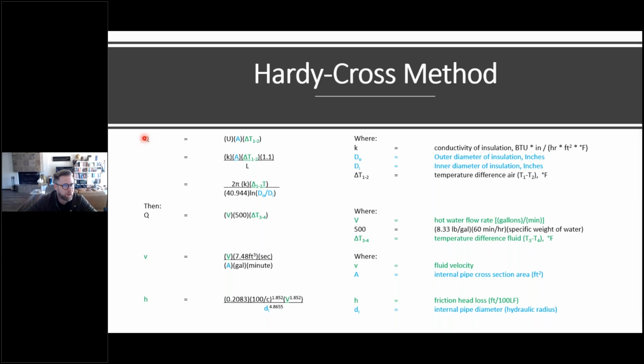So the first one is our conductivity equation, right? Q equals, when we simplify it out, 2 pi times K times the delta T of 1 to 2, divided by 40.944, and that logarithmic root of the outer diameter and the inner diameter of the insulation walls. Then we also have our heat transfer rate for our fluid flow and temperature. We also have a velocity equation, where we don't want to exceed a certain velocity, so we have to figure out our velocity, and that's based off of a volumetric flow times a constant divided by our area. And then last but not least, we have our head friction loss that equals what we just discussed. Basically, that is accounting for our volumetric or velocity losses through the internal diameter of the piping.